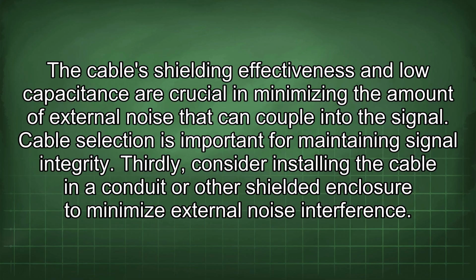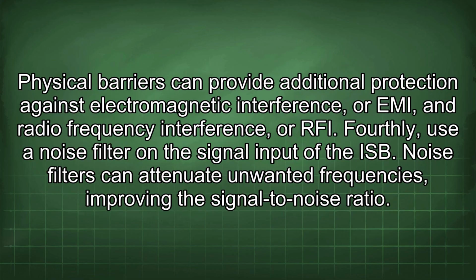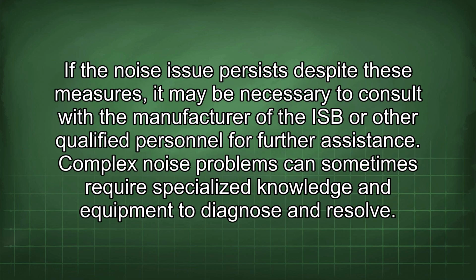Thirdly, consider installing the cable in a conduit or other shielded enclosure to minimize external noise interference. Physical barriers can provide additional protection against electromagnetic interference, or EMI, and radio frequency interference, or RFI. Fourthly, use a noise filter on the signal input of the ISB. Noise filters can attenuate unwanted frequencies, improving the signal-to-noise ratio. If the noise issue persists despite these measures, it may be necessary to consult with the manufacturer of the ISB or other qualified personnel for further assistance. Complex noise problems can sometimes require specialized knowledge and equipment to diagnose and resolve.